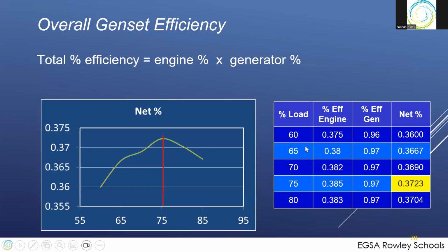So let's put them together. As you know, when you're looking at efficiency, you multiply them together. So it's 0.37 engine efficiency times 0.96 generator efficiency, which gives a net efficiency of 36%. This net efficiency value is plotted on this chart to the left, and we see a definite peak at right around 75%. So 75% of nameplate kW is where this machine is most efficient.